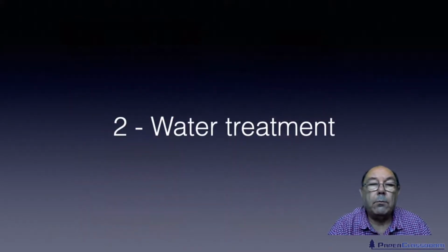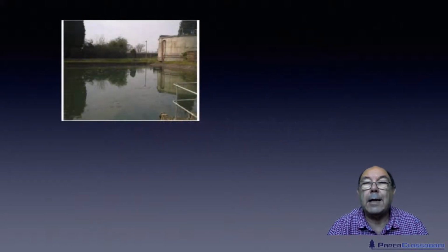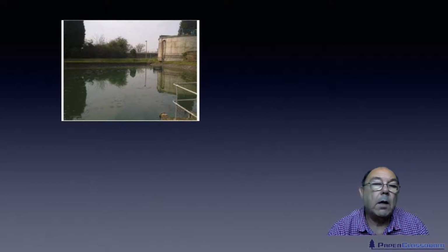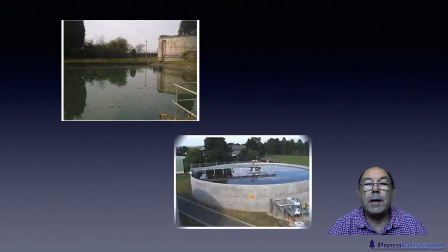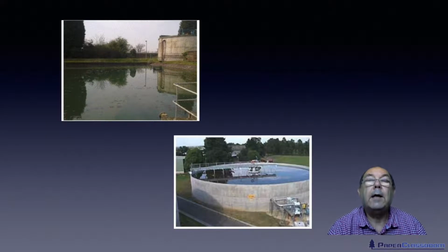Then we need to know a little about water treatment. Essentially, water treatment could fall into 3 categories: flotation, filtration, and sedimentation. When water first comes into the mill pond, it'll undergo a little bit of sedimentation before it passes on to specialised equipment. We might use equipment like this for treating either incoming raw water or even effluent to settle out all the solids and give us nice clear water going into our process.